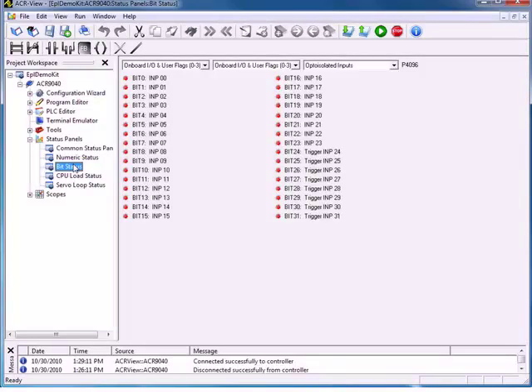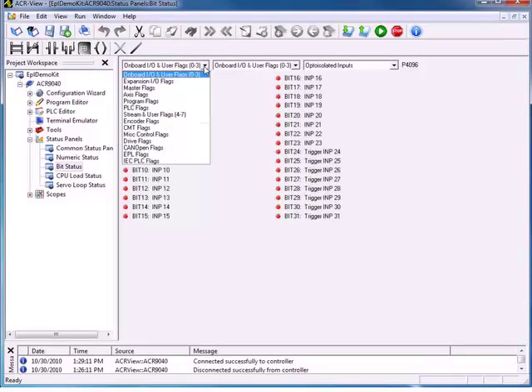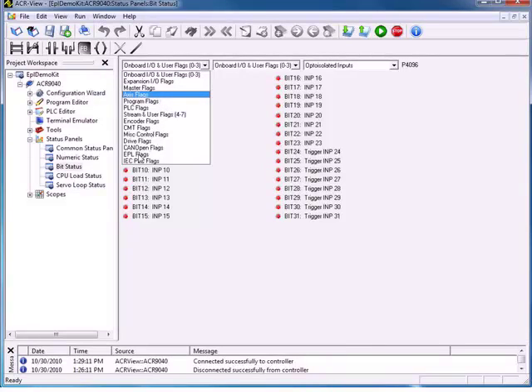We can open this up and see that, besides the onboard IO, we have our expansion IO flags, master flags, axis flags, program flags, and so on, until we come down to EPL flags. Here are our network flags by default. We can see that the EPL controller is installed, the network is operational, and the network start has not failed. So if we're having trouble getting our network to start, we can come here and look at what flags are set.